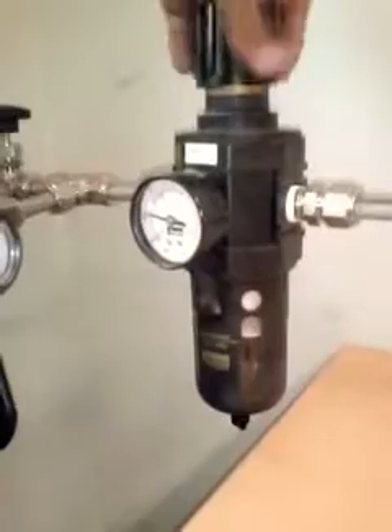As you can see, no pressure on the inlet, so the display is 0.0662 kg per centimeter squared. The reading of the digital processor is 0.07 kg per centimeter squared, equivalent to 4.004 mA. So the LRV is 0, the URV is 250.